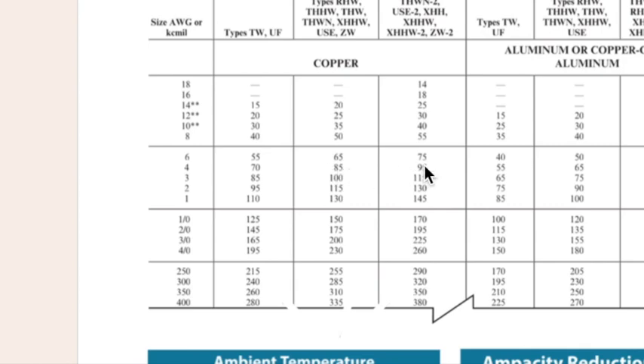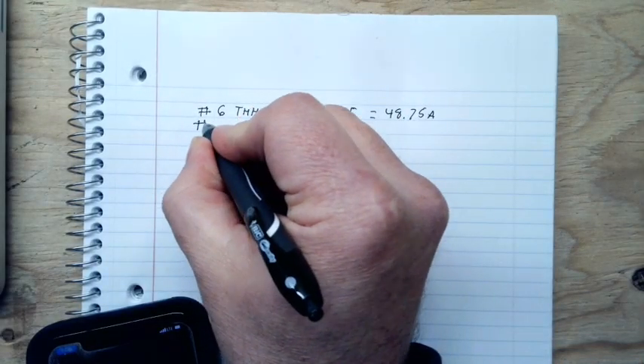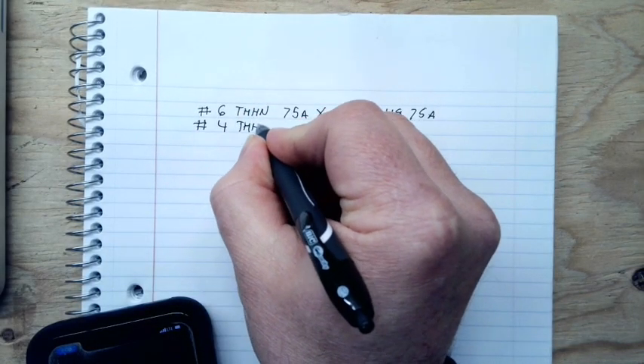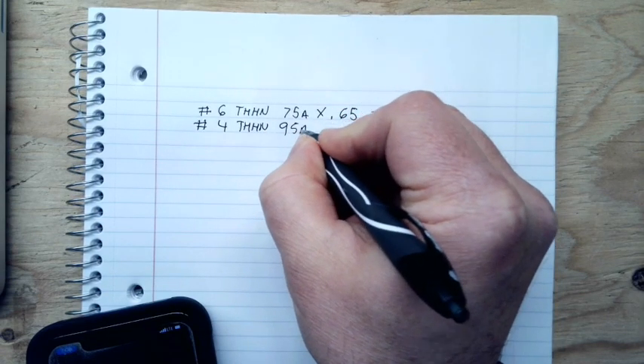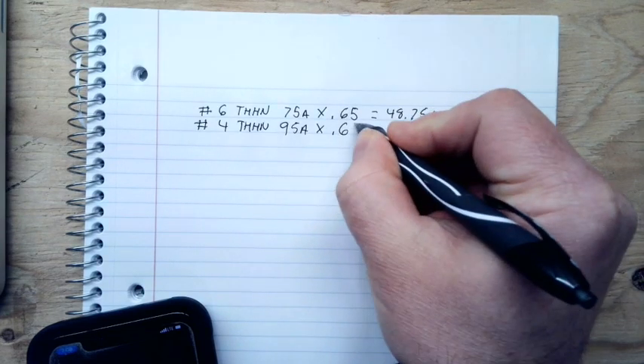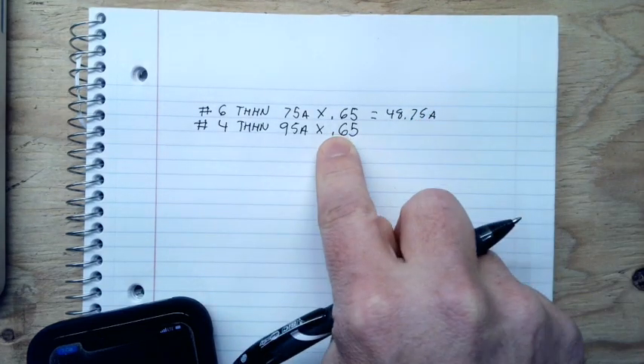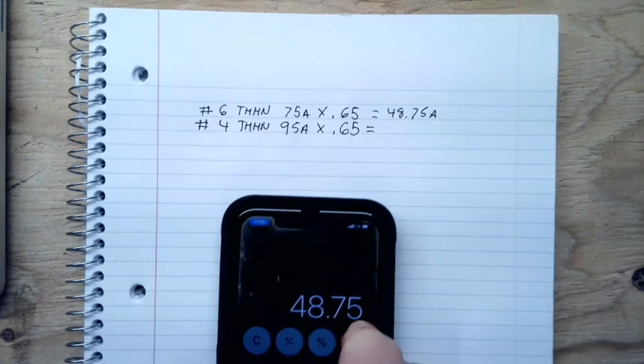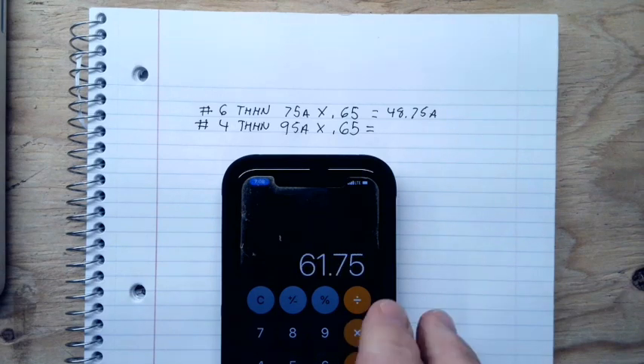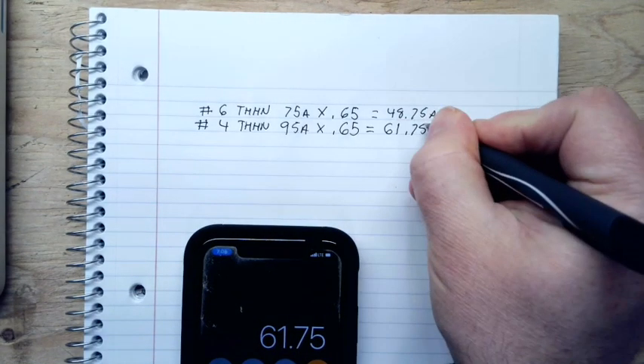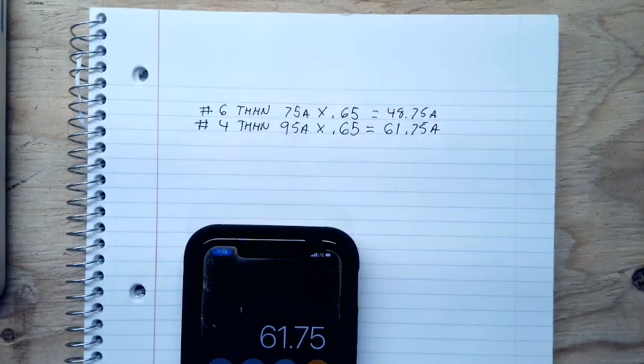So then I'm going to slide over, and that is good to 95 amps. So I have a number 4, THHN, which is good to 95 amps times, now the correction factor won't change, so we can just bring that down. And now that is going to be 95 times 0.65 equals 61.75. Still not good enough to meet our 70 amp that we're looking for. So we've got to keep upsizing.